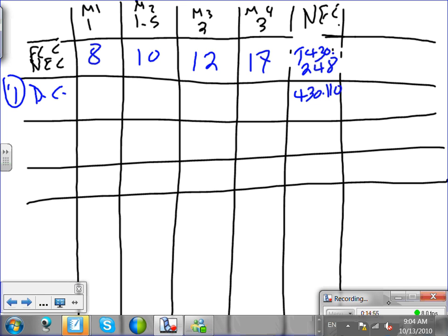Where did the 1.15 come from? 430.110. Why do they do that? Safety. They allow you a little bit, 15% extra amps on the disconnect. Okay, so I'm going to take 1.15 multiplied by 8. Who's going to give me the answer? And the same thing here: 1.15 multiplied by 10, 1.15 multiplied by 12, and 1.15 multiplied by 17. I need two credible gentlemen, or a credible gentleman and a woman.